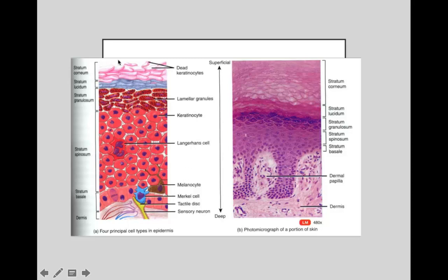So you either have to have a good kind of gel that will penetrate down into these flakes and fill these pores, or else if you think about it, your electrode that you sit on top of here is going to only make contact at certain spots. And also the dead cells don't have the electrolytic properties that a living skin cell would have. This is just an actual photomicrograph of a portion of skin representing the actual presence of these layers.